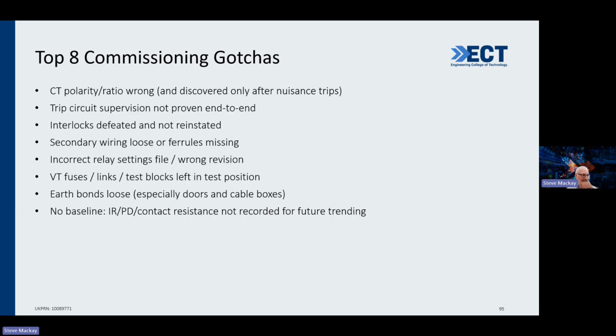In my last few slides, I just want to cover the top 8 commissioning gotchas. Gotchas means things to think about. I'm sure many of you have been through this a million times and will say, I've heard all this before. First, CT polarity or ratio wrong, only discovered after nuisance trips. I've been there. That's a big problem because you can easily connect it up incorrectly, or put the wrong ratio in. Second, trip circuit supervision not proven end-to-end, so it doesn't work.